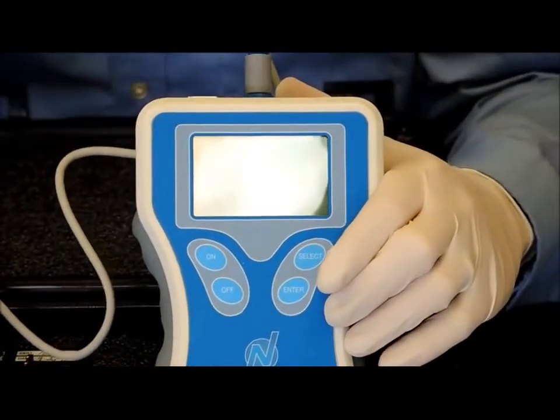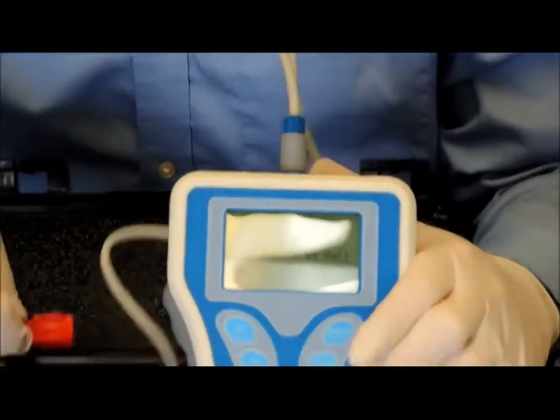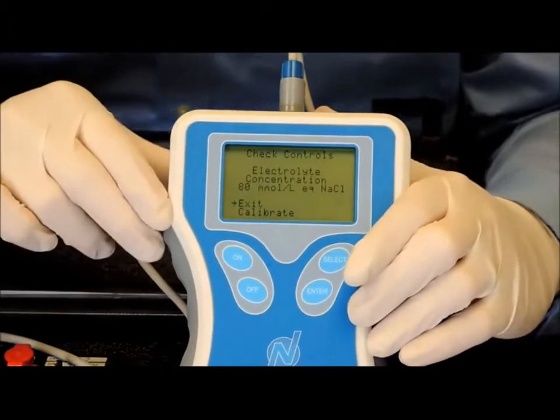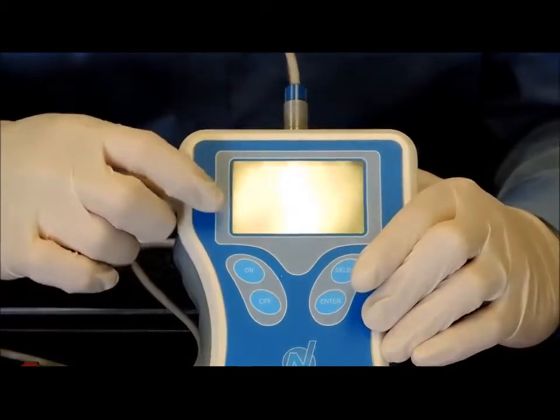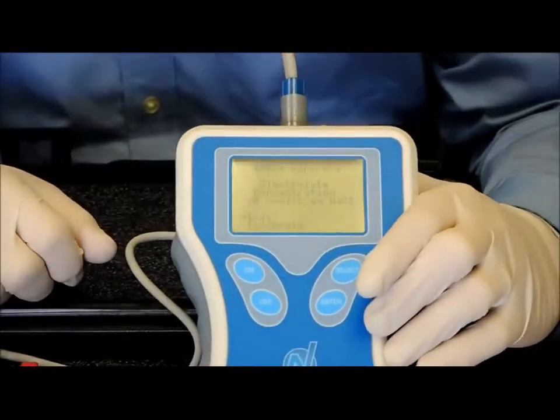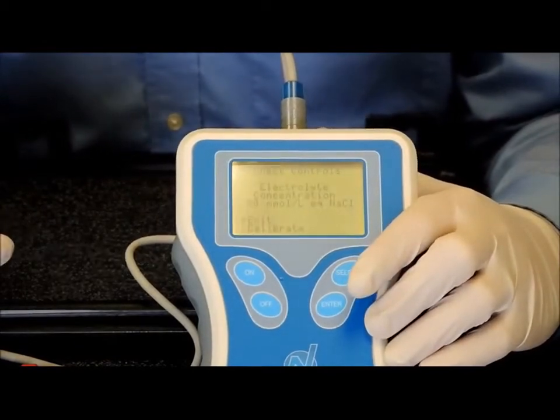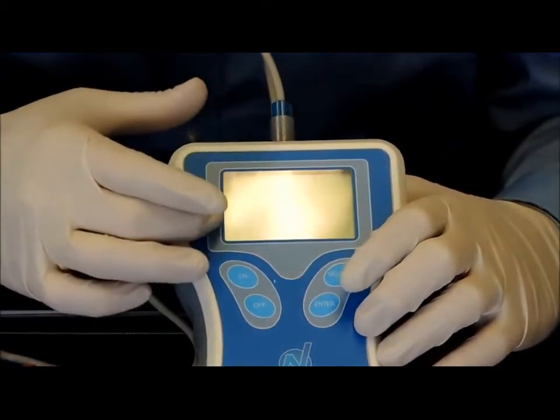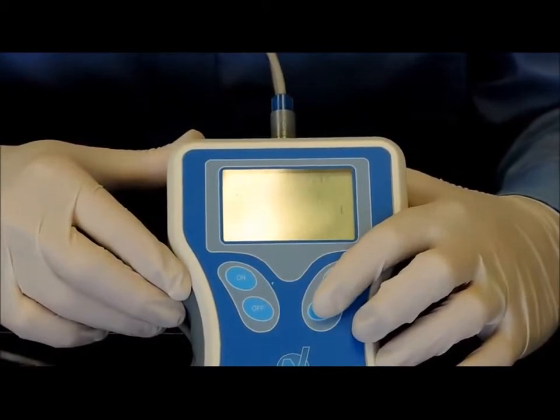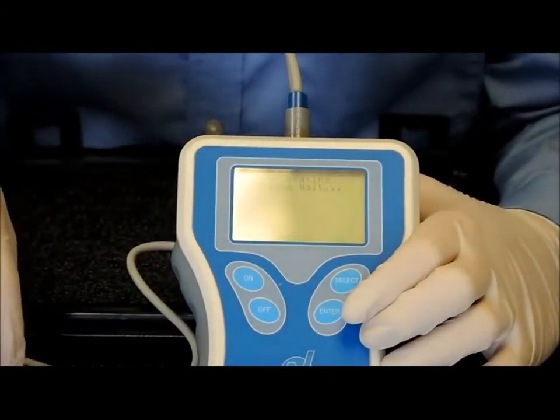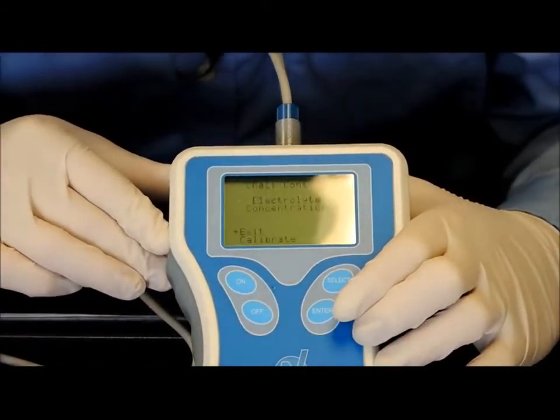The first value you should measure is the 80 value right here. That's the only value that you can calibrate on. And so we attach the sensor to the 80 value, and the screen will show the value when it's attached, and it does read 80. I'm in the habit every day of still calibrating even though it reads 80. So I press select to move the arrow down to calibrate, and then I press enter. And it will go through a process of calibrating to the built-in resistance that's in the calibration plate. Okay, now it's calibrated. It's still reading 80.